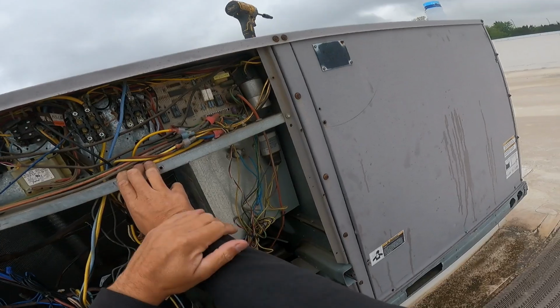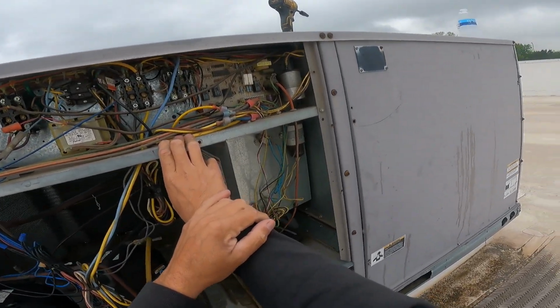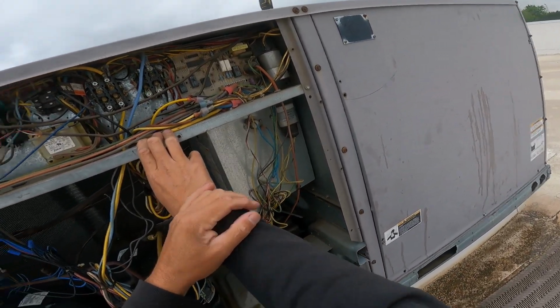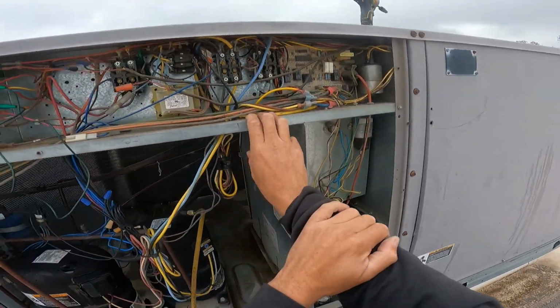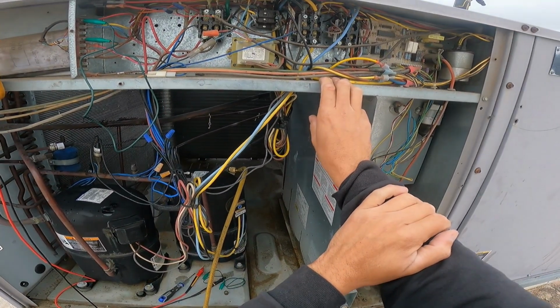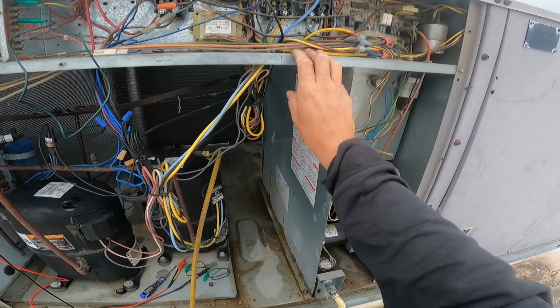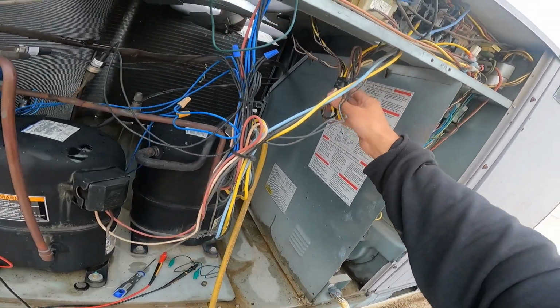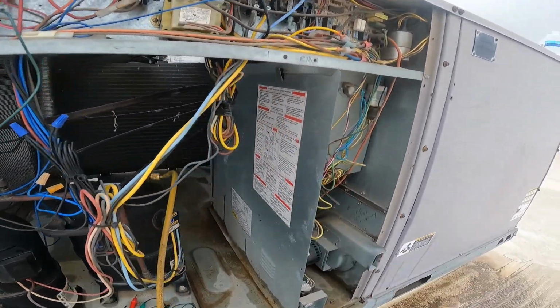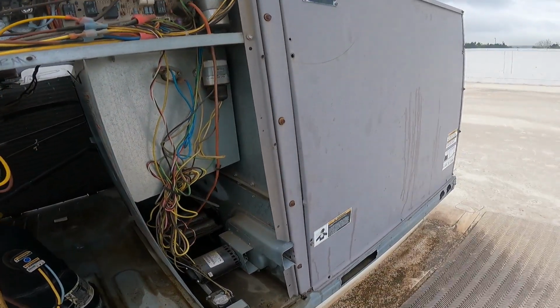Control board looks fine, still got a 3 amp fuse in it, which means we probably haven't had any low voltage issues in the past. I can tell that, oh, that's because we had one condenser fan motor replaced. That's all right, that's all right.